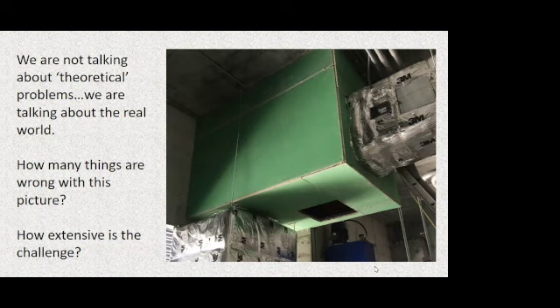They would need to have another wall at the other end, even if it was only 5 feet wide, to hold that end of the box up, right? That's the continuity support required by the design. If we don't put it in, it's not going to stay there during the fire exposure. The contrast isn't great, but if we look in that opening, you should be able to see that there is a lightweight wall stud in the horizontal orientation. That's not going to work in the horizontal orientation. They also did not put in a shaft liner, and they certainly didn't put 2 layers of drywall on.